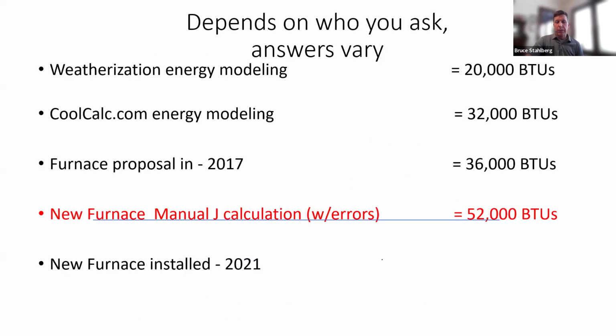So I went out there. This had actually been weatherized by a local agency. They came up with a heat loss of 20,000 BTUs. CoolCalc, which is a Manual J software, I don't actually like it that much. I think it oversizes, but that particular modeling program said 32,000. There was a furnace proposal from another contractor for 36,000, and the furnace that got installed was 52,000.